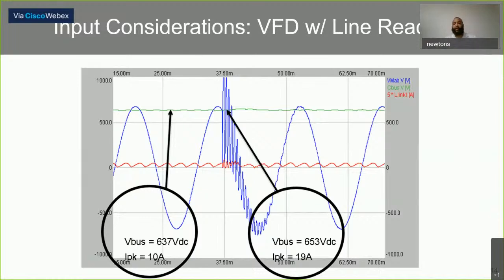And then again, if you look at the bus voltage, it only crept up to 653 volts when the nominal DC bus voltage was 637 volts DC.